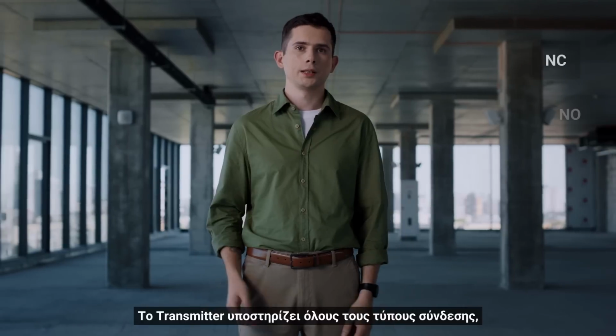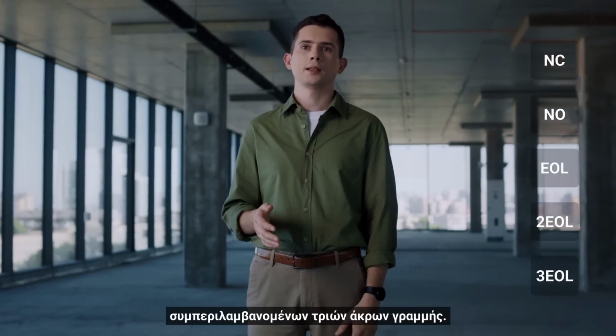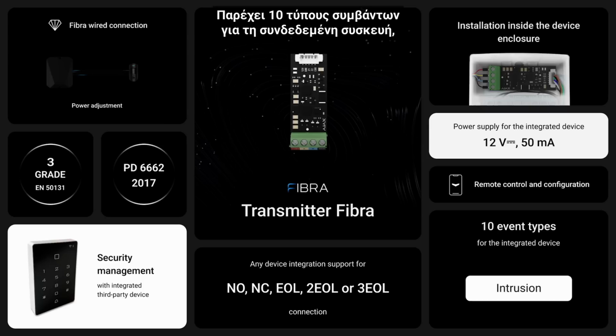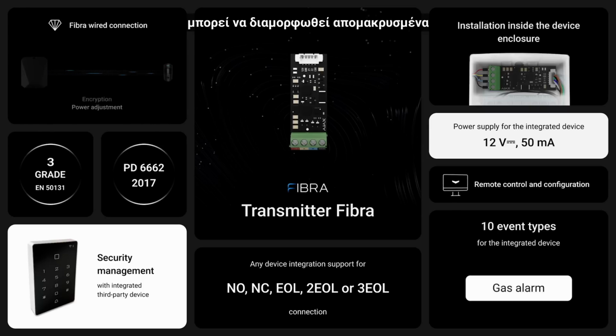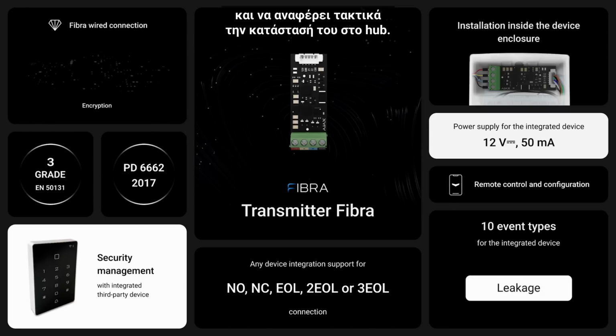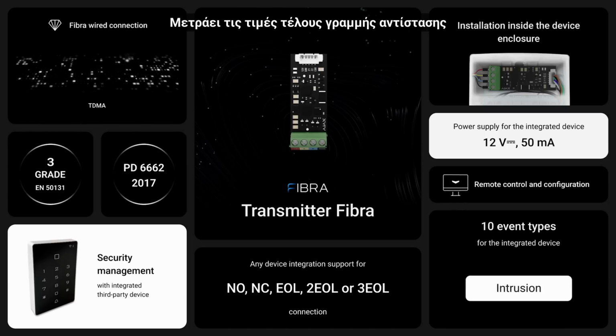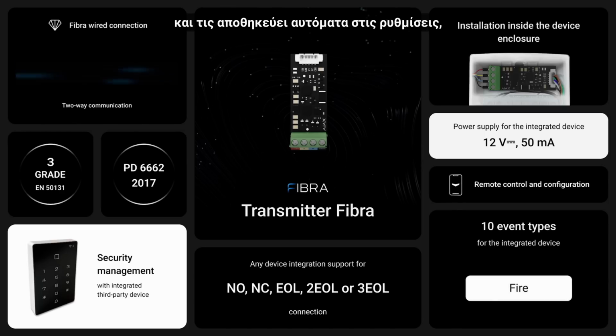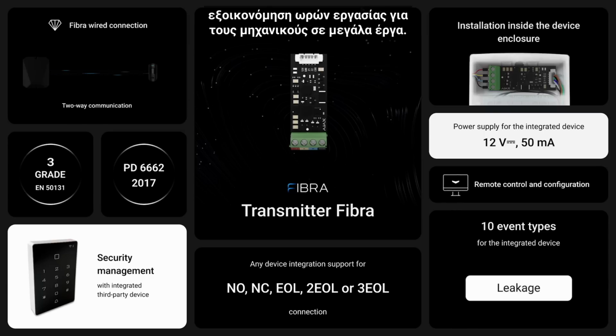The transmitter supports all connection types, including 3 end of line. It provides 10 event types for the connected device, can be remotely configured, and regularly reports its state to the hub. It measures the end of line resistance values and saves them automatically in the settings, saving engineers hours of work on large projects.